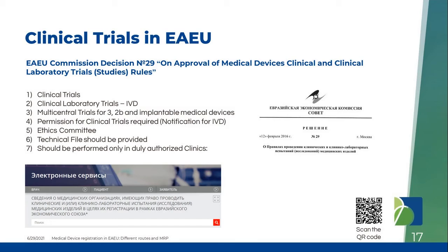So again, the clinical trials should be performed only in duly authorized clinics. Here is the link to the Roszdravnadzor database. Please note, it's not the Eurasian Union database, because Roszdravnadzor's database is a more up-to-date source. The decision number 29 contains the general rules on how you should prove the safety and clinical efficacy of your device, what kind of information and evidence you should provide.